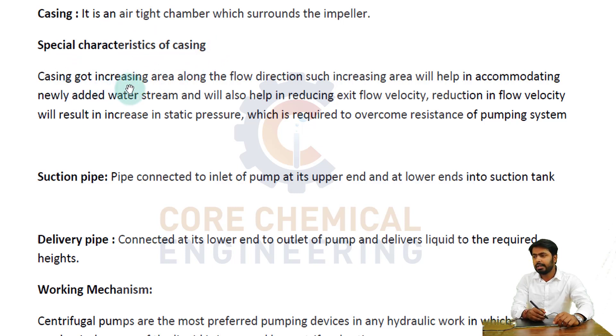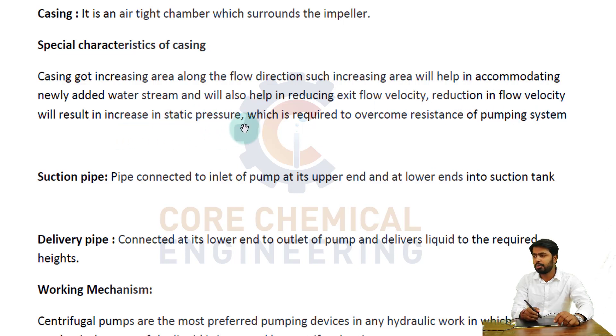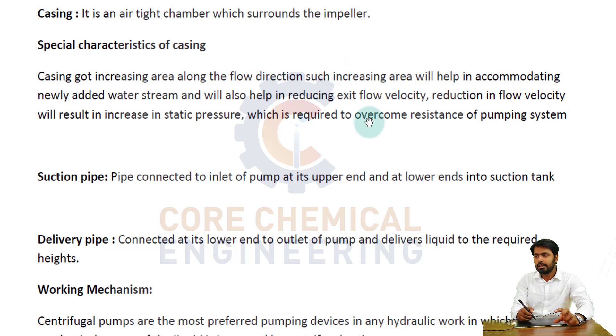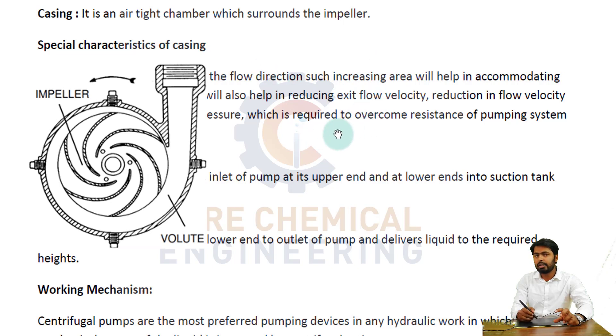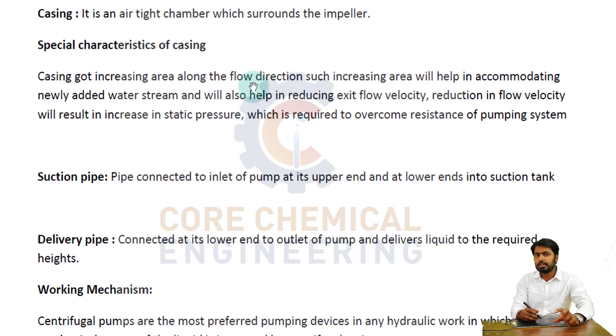Now casing — it is an airtight chamber which surrounds the impeller. The casing has an increasing area along the flow direction. Such increasing area helps in accommodating the newly added water stream and also helps in reducing exit flow velocity. Because as the area increases, velocity decreases and pressure increases. So reduction in flow velocity results in increase in static pressure, which is required to overcome resistance of the pumping system. The casing has a volute shape with an increasing cross-sectional area as fluid moves toward the discharge.